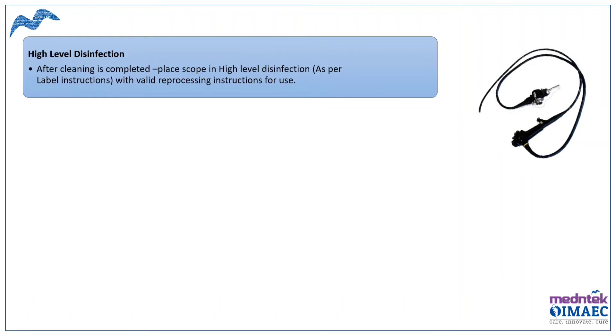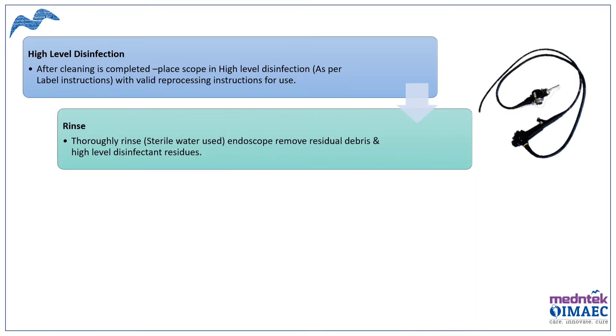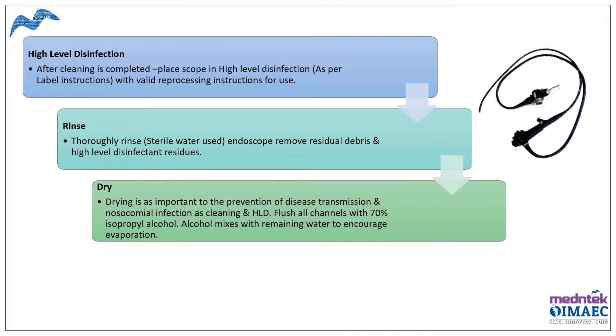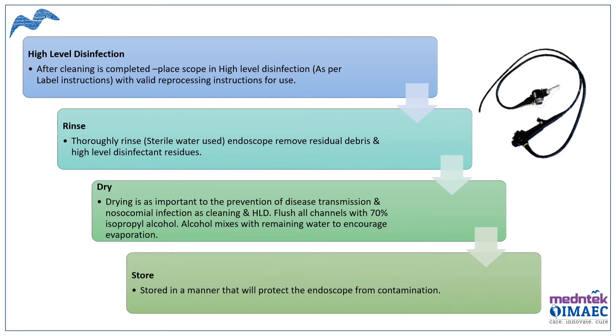After pre-cleaning, the next step is high-level disinfection, in which the endoscope is immersed in the high-level disinfectant according to the reprocessing instructions. Following high-level disinfection, the endoscope is rinsed with sterile water to remove residual debris or any residues of disinfectants. Next, drying is performed using 70% isopropyl alcohol, which acts as a dehydrating agent. Any moisture remaining in the endoscope facilitates the growth of microorganisms, making drying a critical step. After proper disinfection and drying, the endoscope is stored following proper protocols to avoid further contamination.